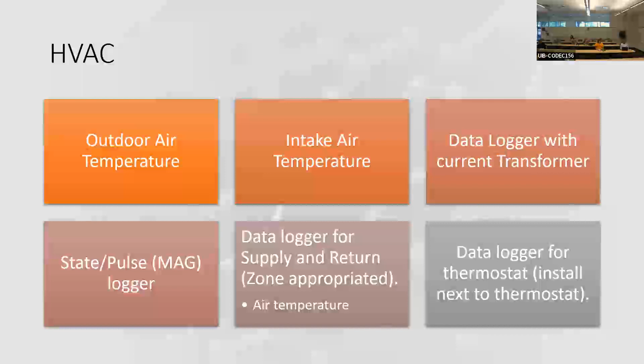And then having a data logger regarding air temperature, humidity, and if you want, CO2 or VOC as well, for the supply and return. Make sure it's zone appropriate. So you want to make sure the rooftop unit you're monitoring is the one supplying the zone you're also monitoring. And then also a data logger for the thermostat. Next to the thermostat, we're just verifying that the thermostat is operating as it should. If it says it's 72 and we put a sensor next to it, it should also read 72.